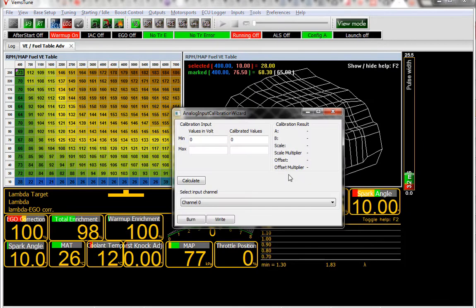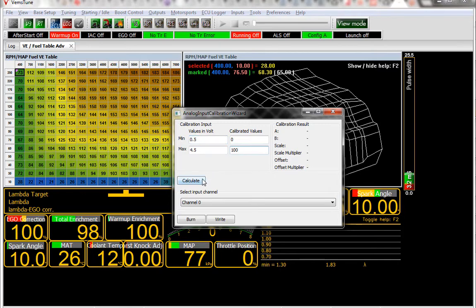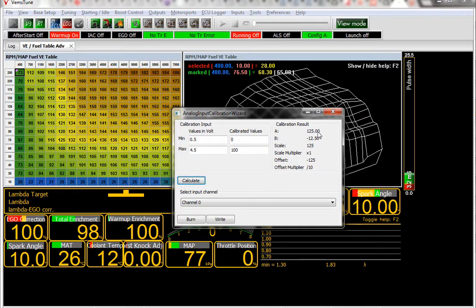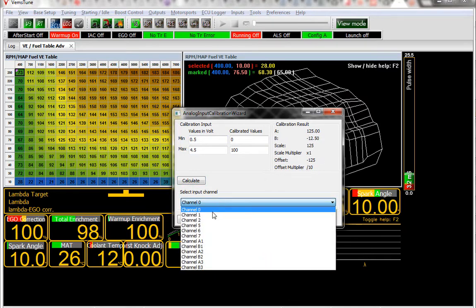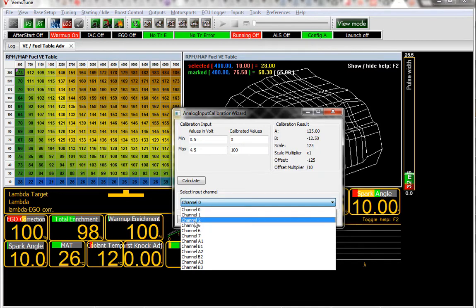Analog Input Calibration Wizard. Our sensor is 0.5 to 4.5 volts, gives you 0 to 100 PSI. He bought one of the sensors from us. You can get this from the website. Click on Calculate, and it gives you some results right here. It's simple, you just select the channel that you're connected to. We have, on the bench, it's connected to Analog Channel 2. So you just choose Channel 2 and burn it. And that's all.